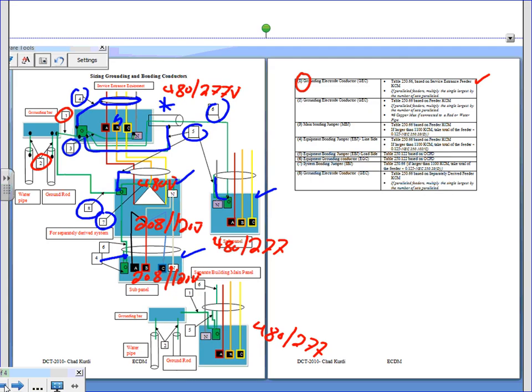One is going from the switchgear to the grounding bar. This one is going from the grounding bar into a pipe or a rod. That's the difference between them, where they are used, but they're the same type. It's a grounding electrode conductor. My question: number 1, you said 3-aught, and this one is number 6. So how could they be the same type? Code 250.66(A), because it's going to a rod or a pipe. They're called grounding electrode conductor, but they're used differently.